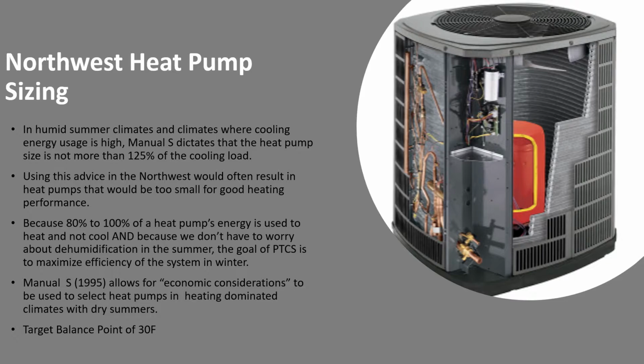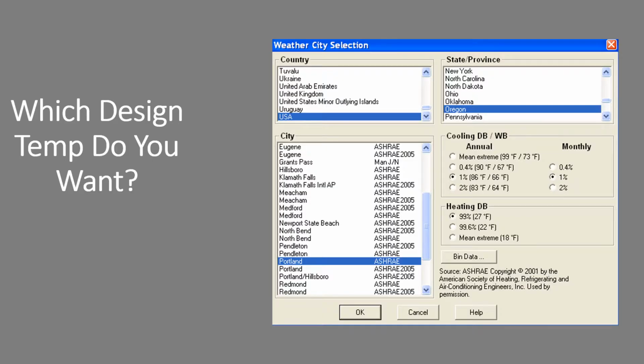If you're really into reading ACCA manuals, Manual S says, boy, if you don't live in a humid place and you're in a heating dominated climate, you can use economic considerations. And there's been a lot of research done in the Northwest to prove that those economic considerations point to a target balance point of 30 degrees Fahrenheit. Which design temperature do you want to use? I have seen heat loss calculations turned in using the wrong city.